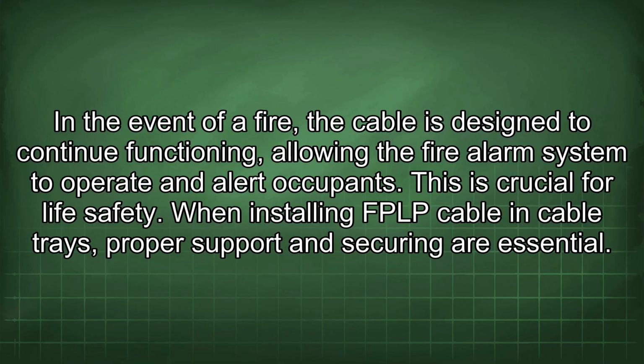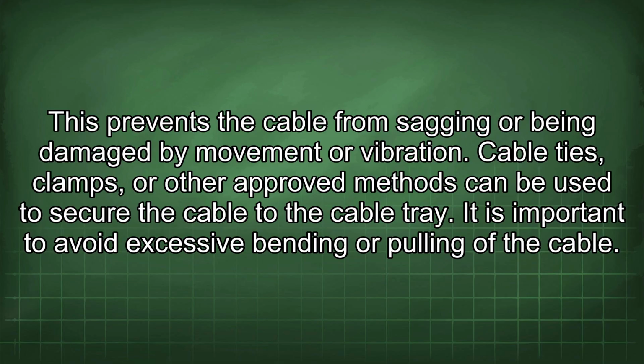When installing FPLP cable in cable trays, proper support and securing are essential. This prevents the cable from sagging or being damaged by movement or vibration. Cable ties, clamps, or other approved methods can be used to secure the cable to the cable tray.